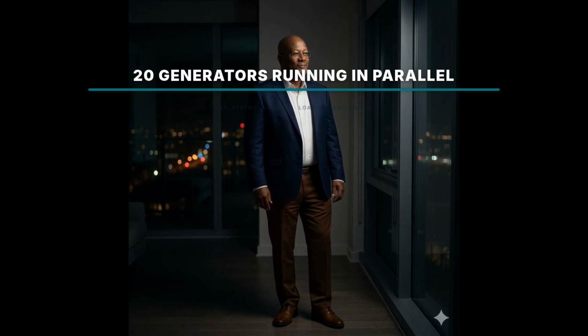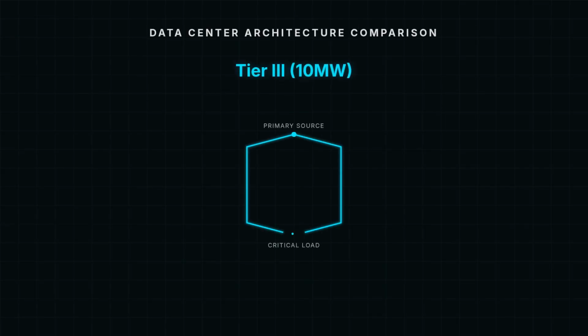Building the machine at Hyperscale requires absolute, uninterrupted continuity. In Series 1, we looked at Iron Gate. Its UPS architecture was a standard 2N setup, two complete systems, each capable of carrying the full IT load. It was the correct engineering specification for a 10 megawatt Tier 3 facility, but at FULCRUM, we have moved beyond standard limits. FULCRUM, however, is a Tier 4 equivalent campus.